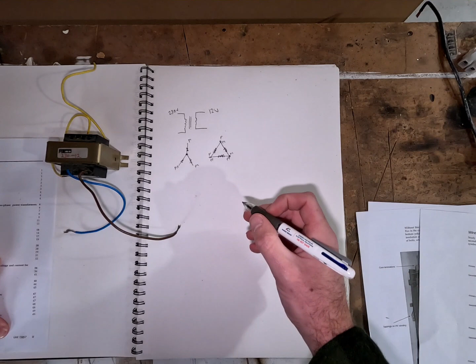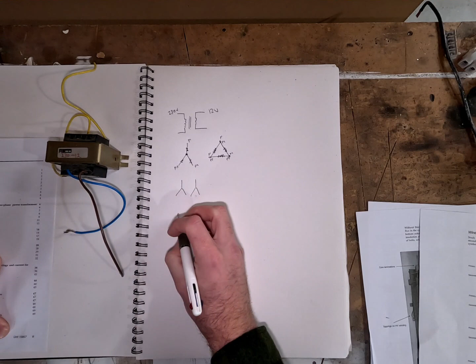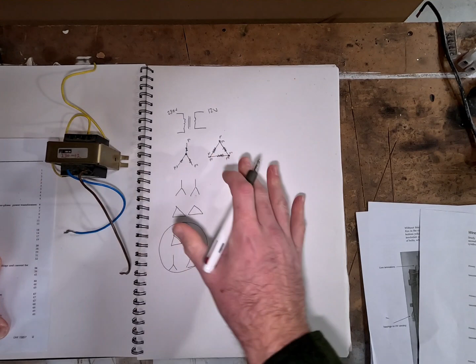Now, the different ways you can connect them are star-star. This is on the transformers, so this star will induce directly onto this star. You can have them delta-delta, same again, from the one delta to the other. You can go delta-star, and you can go star-delta. These last two are the most common for three-phase transformers in New Zealand, but you do have the others as well in other applications.